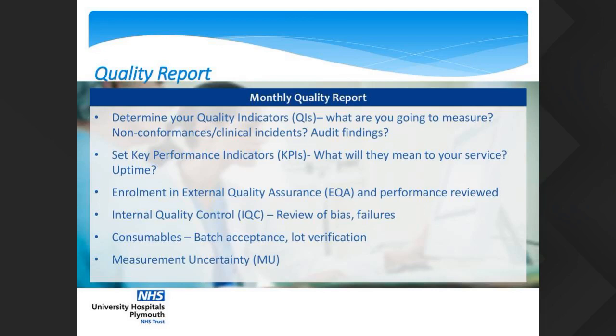And measurement uncertainty, there's a number of different calculations you can use for that, but you need to communicate to your users what the uncertainty is around every measurement that is made using blood gas analyzers. So if, for instance, sodium on a blood gas analyzer is reported as 140, is that actually 140, or is it 139 or 141 if you have a measurement uncertainty of 1 millimole, for instance? In your verification and validation of each of the analytes performed on the blood gas analyzers, you need to have assessed that, quantified it, and then communicated that to your users, because in my first talk I talked about interpretation of results, and the end clinician needs to know if that analyte doesn't perform as well as the main laboratory, or whether there is a constant bias, and that needs to be taken into the interpretation of the result and obviously the clinical decisions being made for that patient.